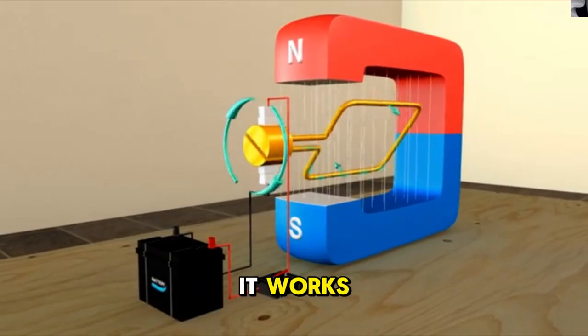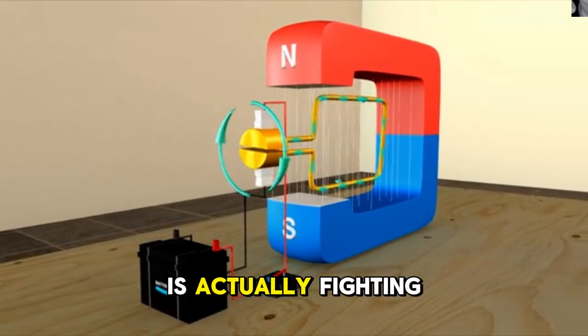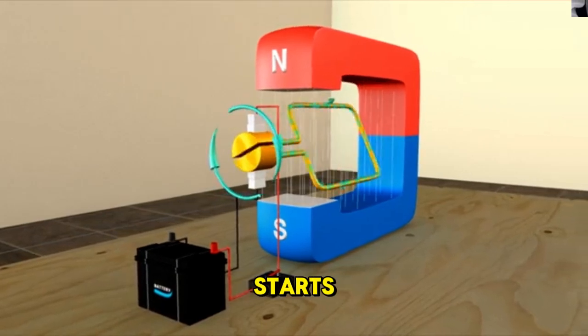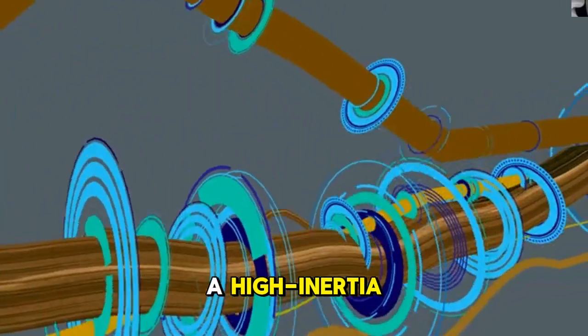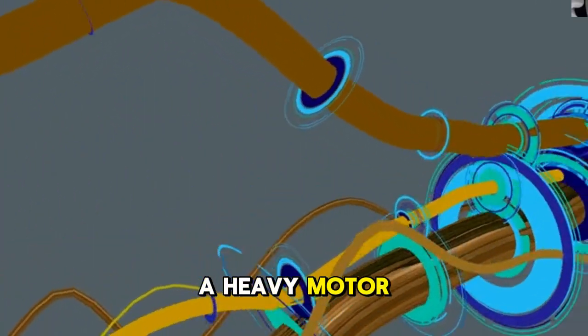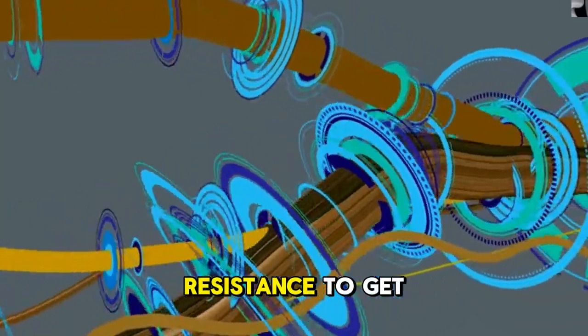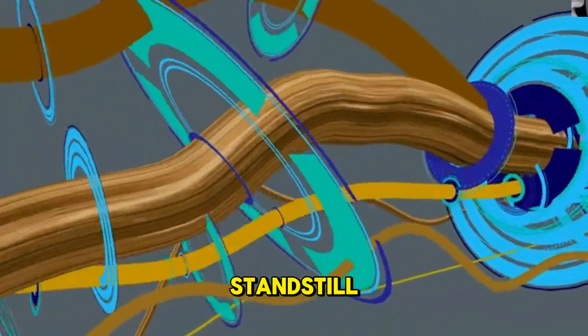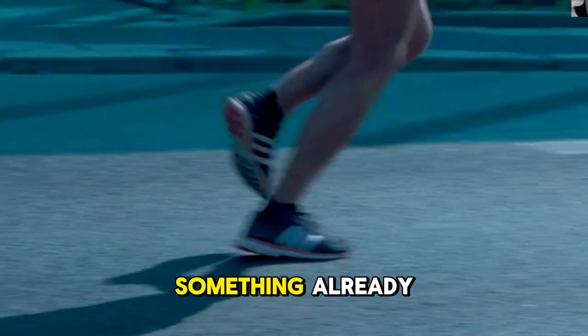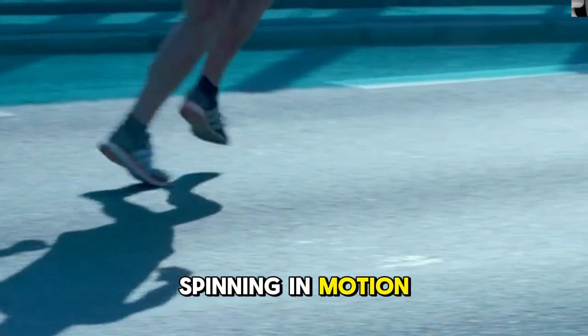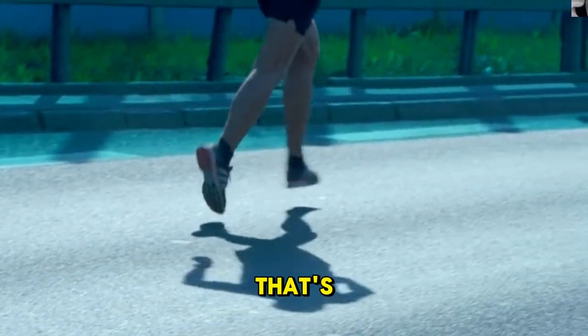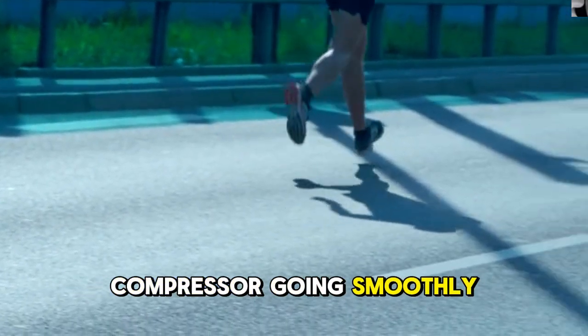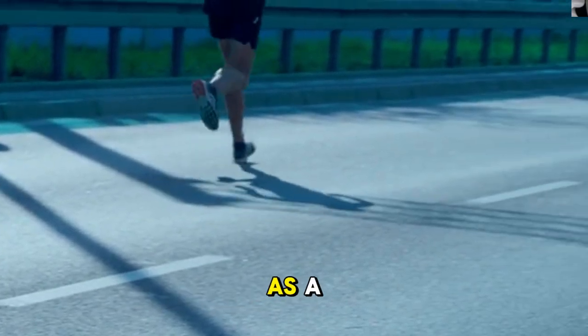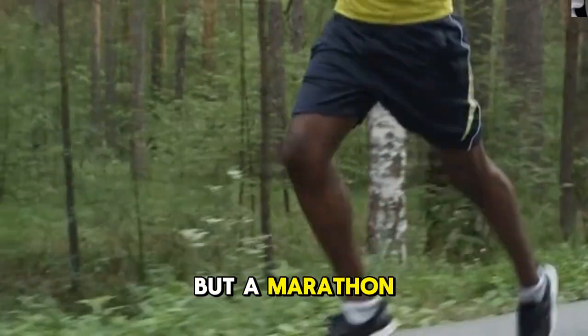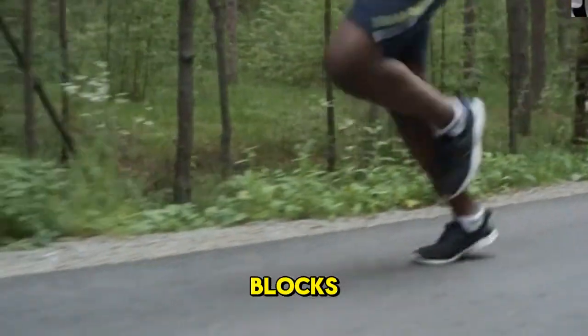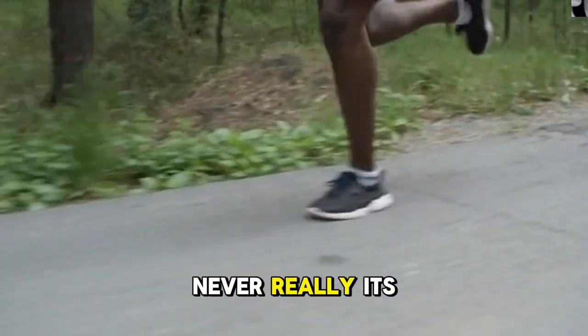To understand why it works, you need to understand what your compressor is actually fighting against when it starts. Engineers call it a high inertia load. Basically, a heavy motor that has to physically overcome its own resistance to get moving from a standstill. That first push takes far more energy than keeping something already spinning in motion. Your AC has a run capacitor that's excellent at keeping the compressor going smoothly once it's up to speed. Think of it as a great marathon runner. But a marathon runner isn't built to sprint out of the blocks. That explosive first push was never really its job.